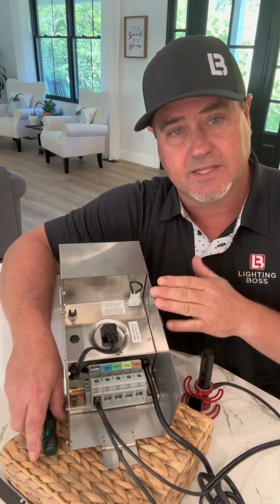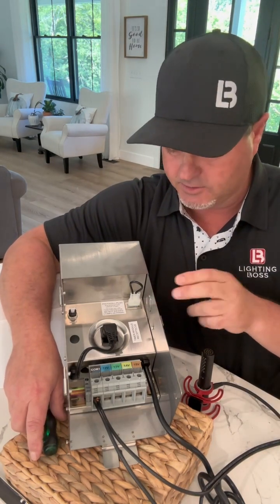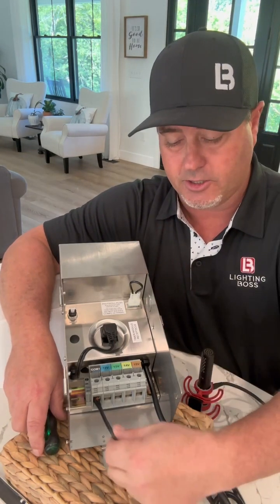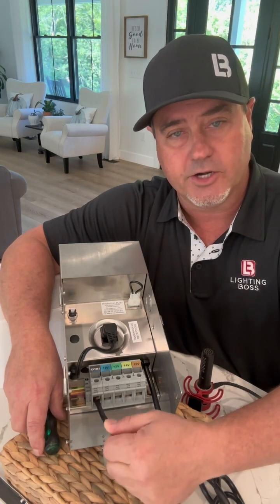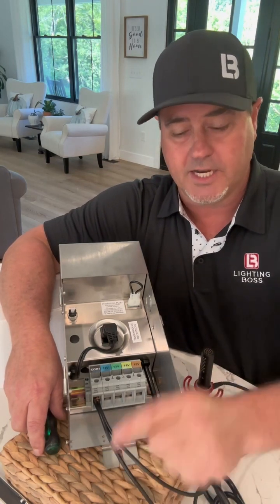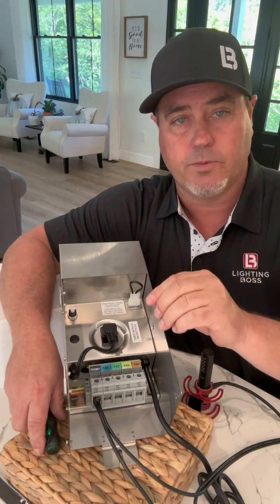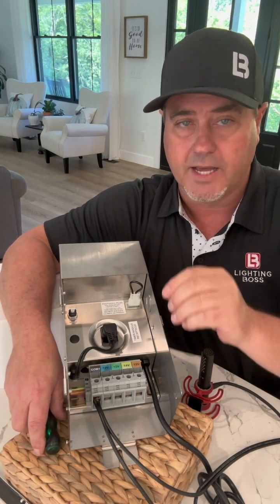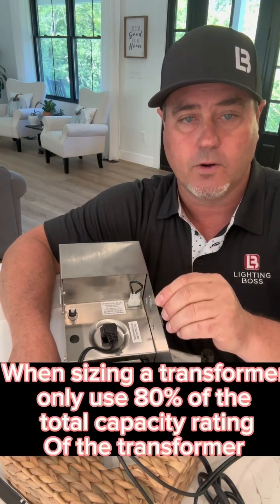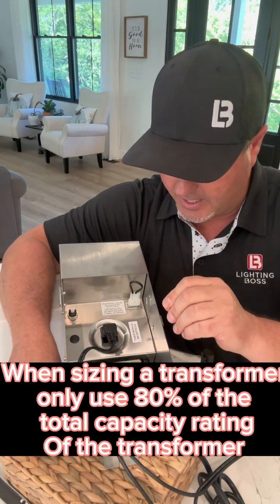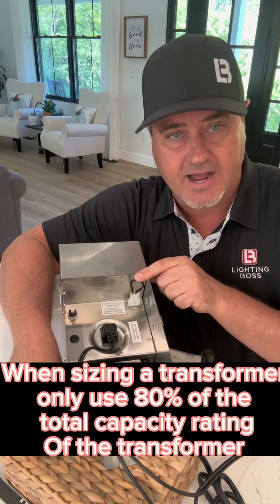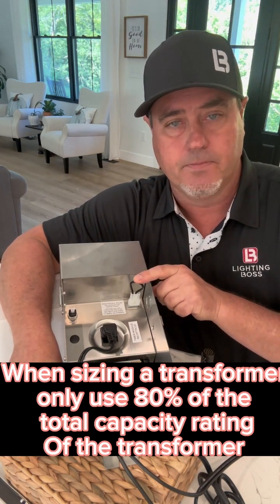These are some of the basic things that you need to be testing. So just to review, you want to test your amp load down here on your secondary side, and you'll take a look at the transformer you're working with to refer to. For most transformers, on a 300 watt, it is around 25 amps. And on the primary side, you're looking at 2.5 amps. So this is a transformer made by Light Tech.